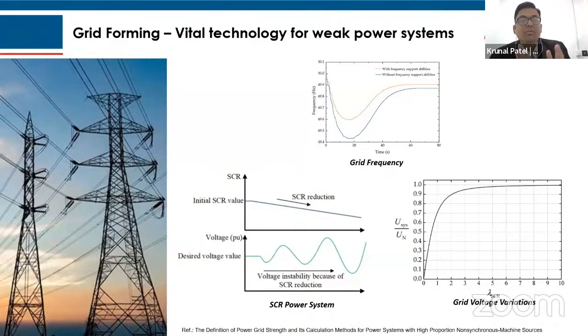Because of power electronics versus synchronous generators, the short circuit ratio is very different. By adding grid forming technology, we are trying to maintain a short circuit ratio equivalent to that of the synchronous generator. You can see very clearly in this graph that as the short circuit ratio reduces, the voltage fluctuation becomes more and more. To avoid this kind of scenario, the grid forming inverter plays a very important role.